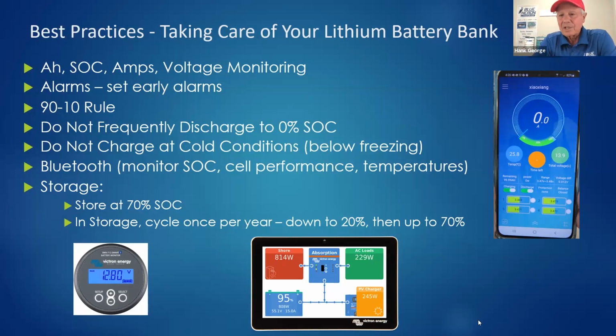Much better just to pay attention to amp hours. How many amp hours am I down? I'm down, whatever, 250 amp hours out of a 1200 amp hour bank. I'm in good shape. You can look at state of charge, and the only caution there is that state of charge will work pretty well once it's been calibrated. If the Victron BMV 712, for example, its default settings will not give you good state of charge readings on lithium. You have to set it to proper settings. And then it has to go through a calibration cycle. And over time, once it's done a calibration cycle, it will read pretty well.